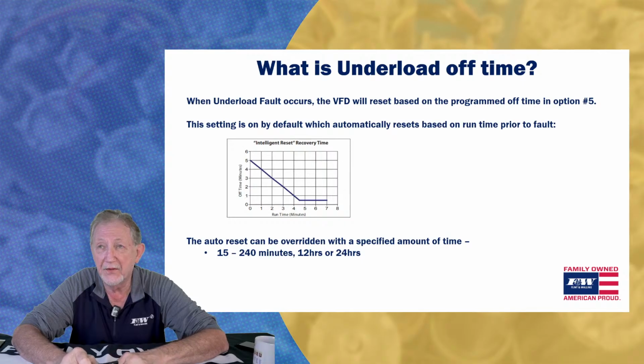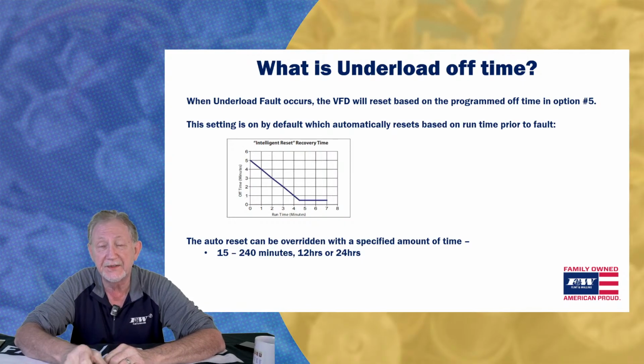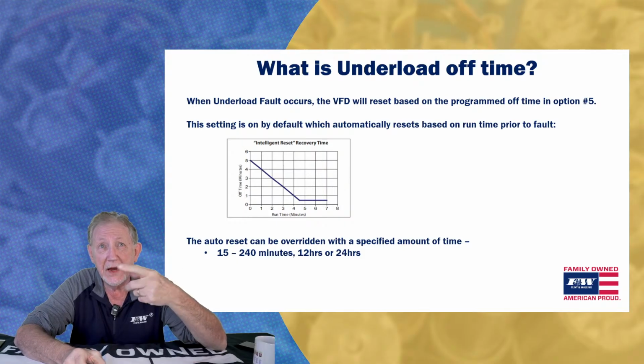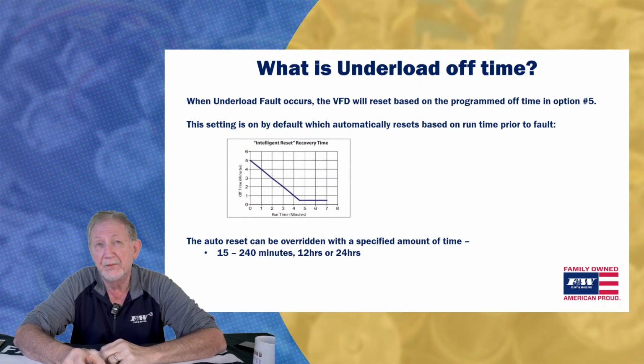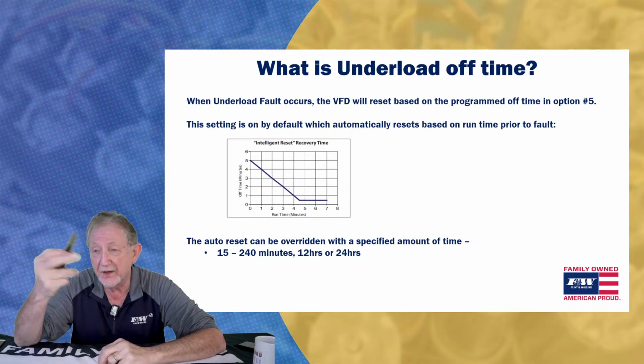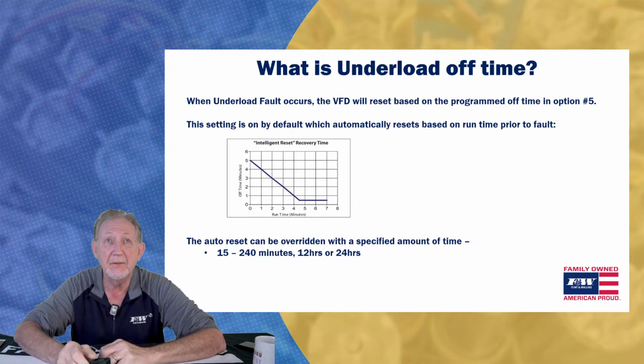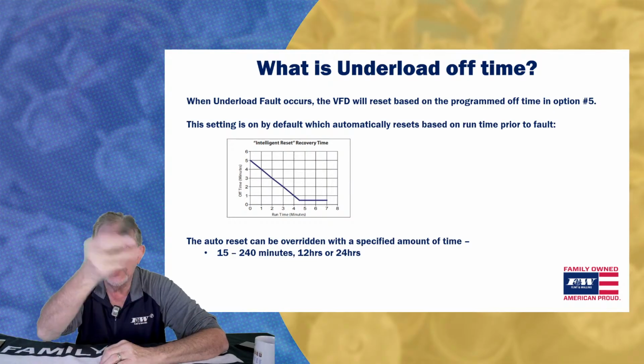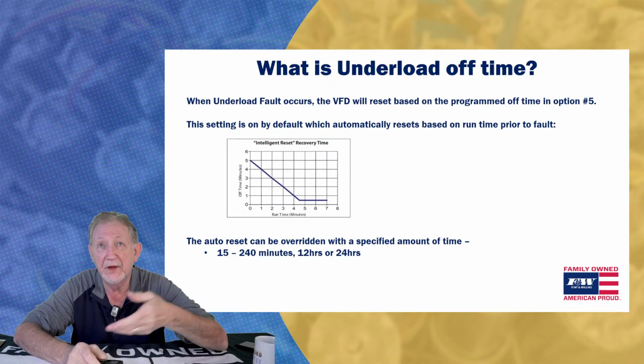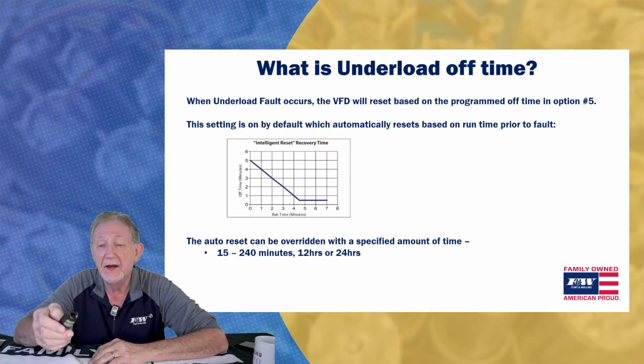I think after about the third time that happens, it will go into a hard fault, and it's going to basically stay off. You can override all that. Again, go into the program, into that menu, hit edit, and you can reset that timer, the time that it's off. You have that ability with the up and down scroll buttons, okay?